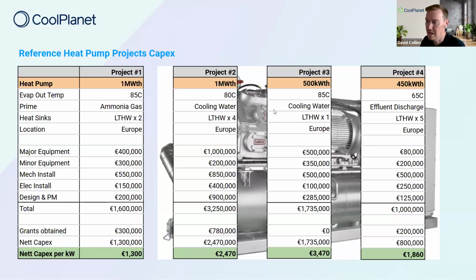So it's kind of hard when you look at that slide to say there's a rule of thumb. It's very much going to be between 1,000 and up to 3,500 euros per kilowatt installed, but it very much does depend on the application on site, how far you need to route LTHW hot water pipework, and how many heat sinks you're interfacing with as well. And in the case of this first project as well, the complexity of integrating directly with ammonia gas also has its challenges from a point of view of control and mechanical installation.